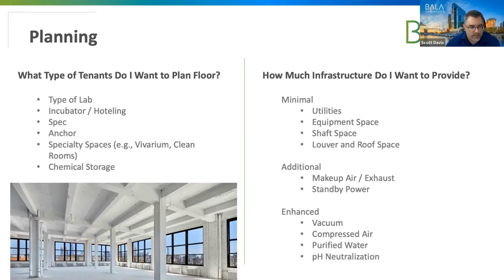With the enhanced systems, it comes down to the type of lab we're laying out. If we have an anchor client taking a large portion, if not all, of the space, these enhanced plumbing systems may go in because they control everything. But if we're dealing with a more varied tenant space with a lot more tenants, these enhanced systems may be pushed onto the tenant to provide their own. With pH neutralization or waste neutralization, there might be common riser stacks for them to dump their treated waste, but the actual treatment system falls onto the tenant.